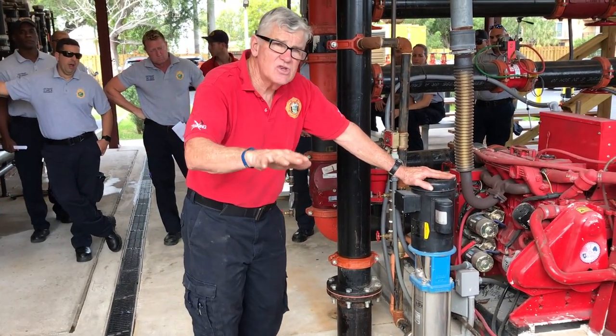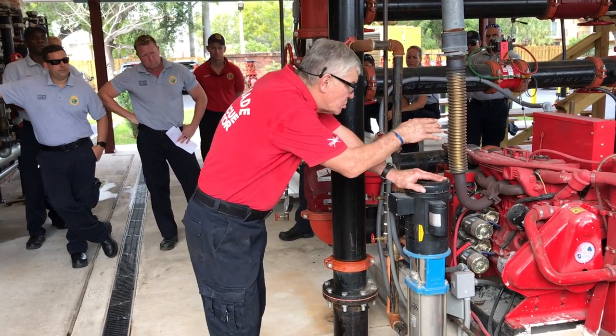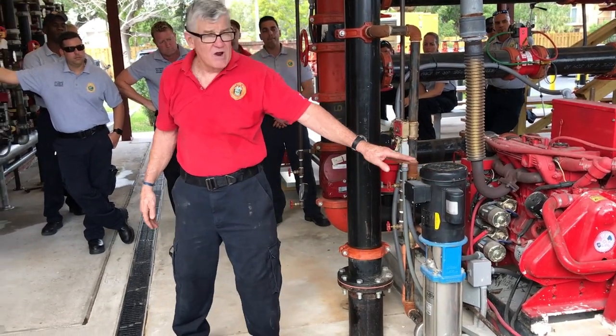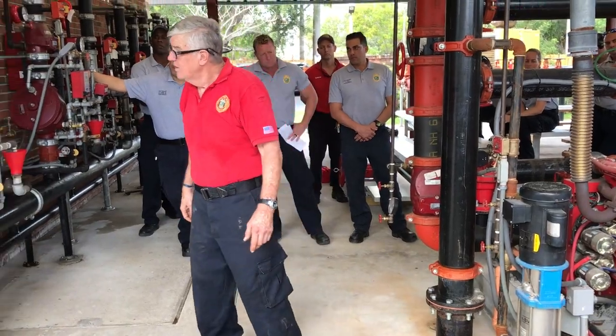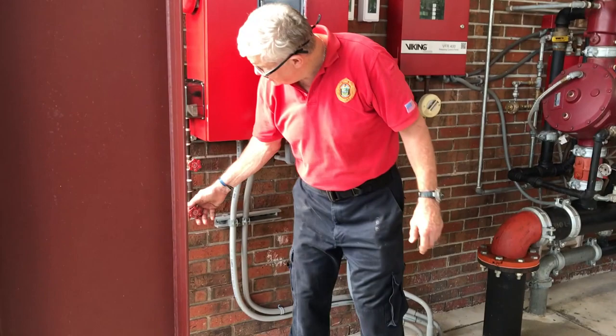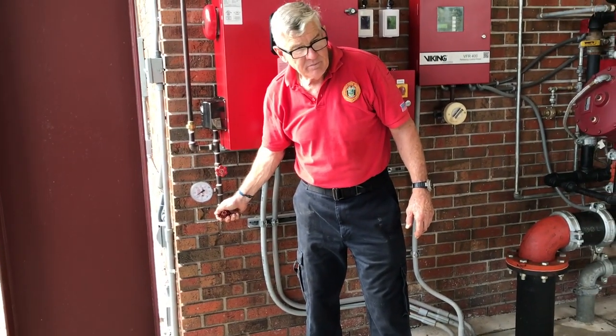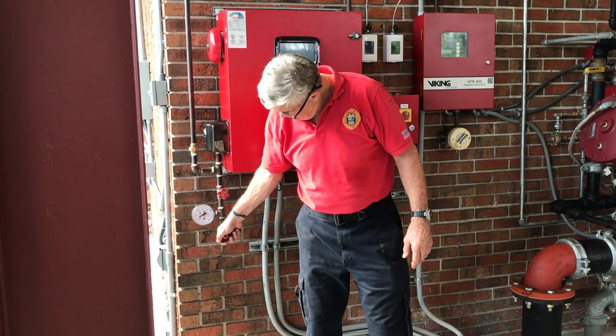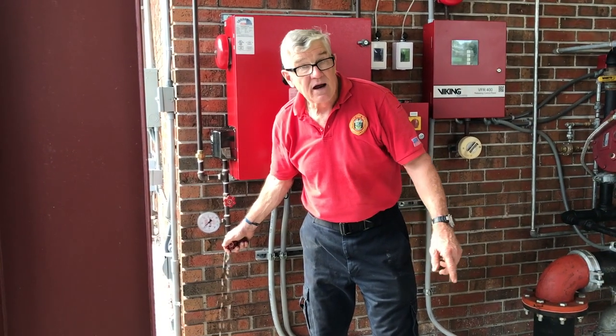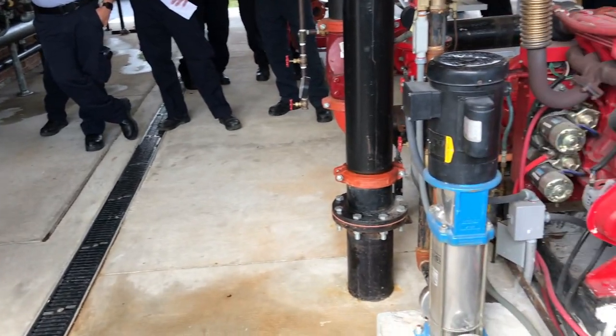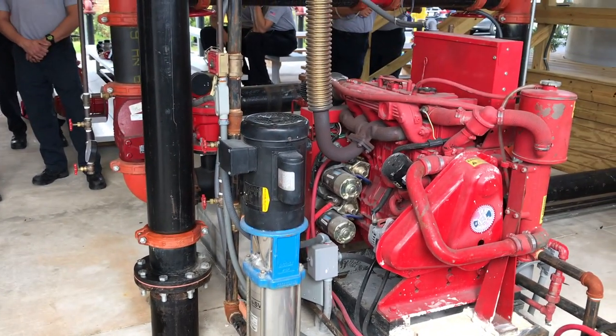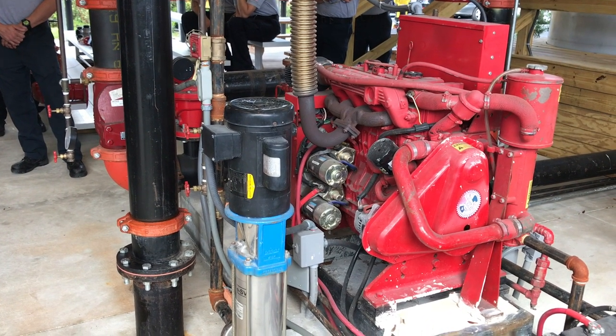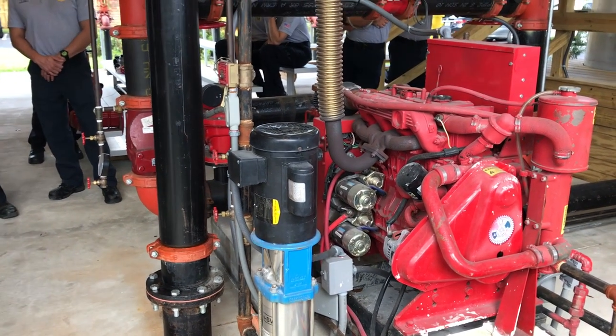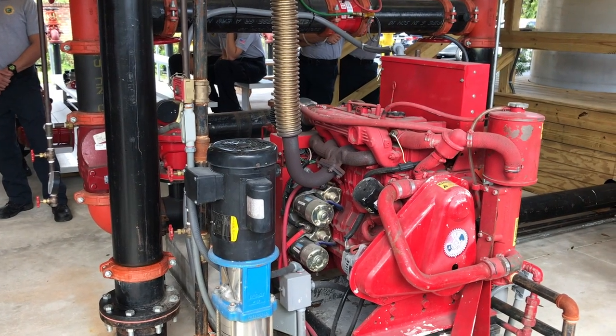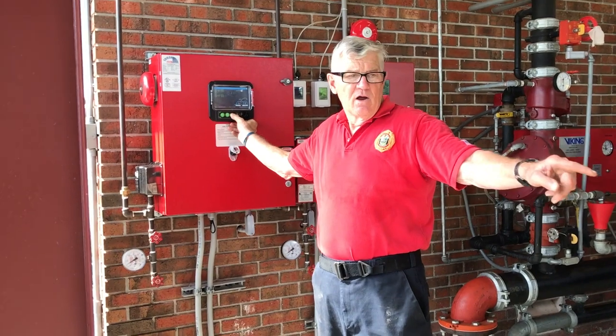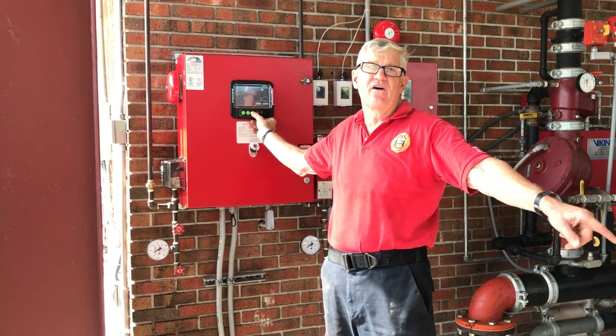Again, if you drain the system and you need to refill it, shut the fire pump off, operate the jockey pump. Do not use the fire pump because it's going to cause a water hammer. So if we just crack this, what's just flowing through the relief valve for cooling.